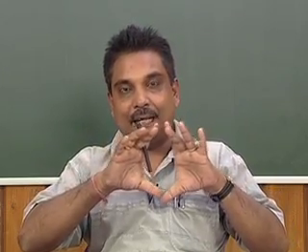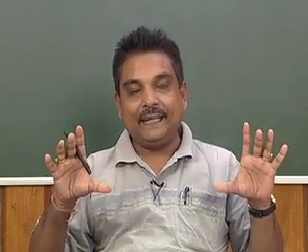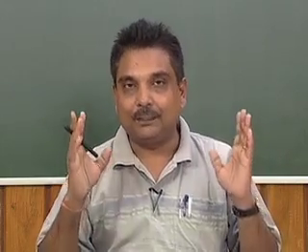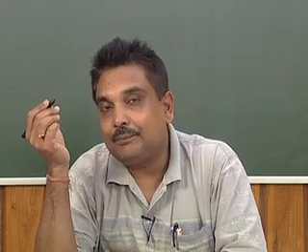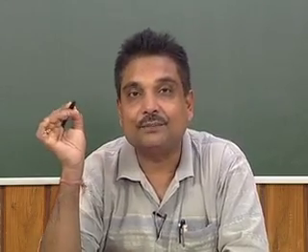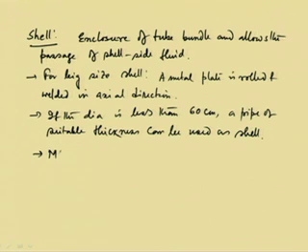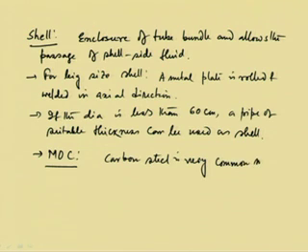So, the shell is a bigger diameter pipe. That pipe is made either by rolling a metal plate and then welding, or by just cutting a suitably sized bigger pipe piece, which can be used as a shell. The purpose of the shell is that the tube bundle will be placed inside, and it will help the passage of the shell side fluid. The material of construction is also very important for the shell. The material of construction, MOC, is usually carbon steel, which is a very common one.